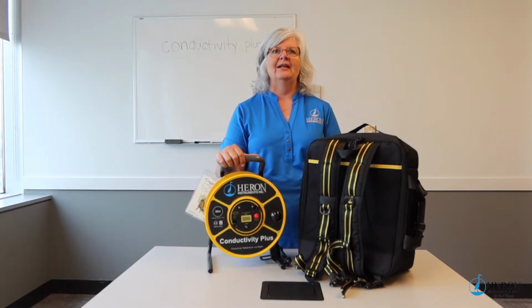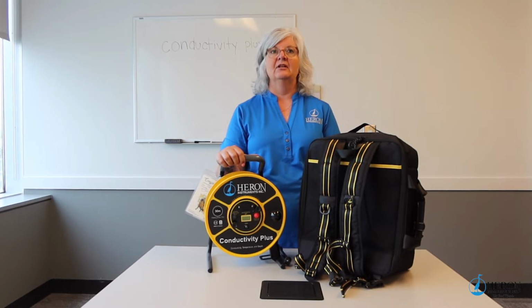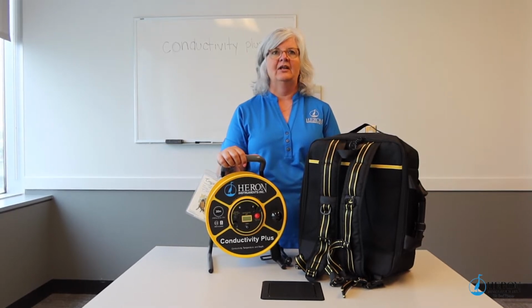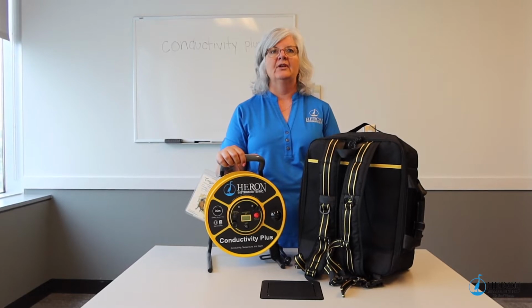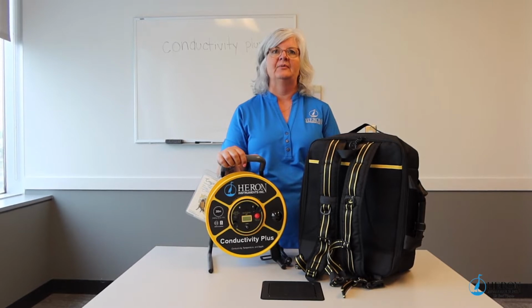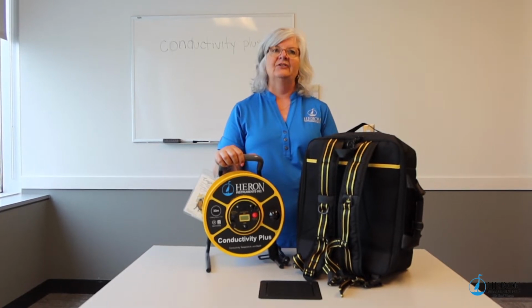Today we're going to demonstrate how to use the Heron Series 1700 Conductivity Plus water level meter. The Conductivity Plus enables accurate measurements of conductivity, temperature, and water level in wells, boreholes, standpipes, and estuaries where salt water intrusion and contamination levels become a concern. Conductivity can be an early indicator of changes in the water system due to fluctuations of salinity in water. An LCD screen displays conductivity values up to 80,000 microsiemens and temperature ranges from 0 to 50 degrees Celsius.